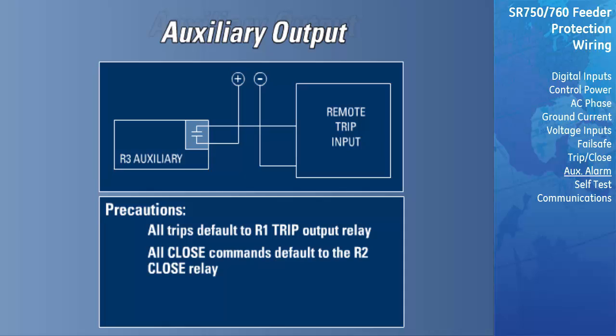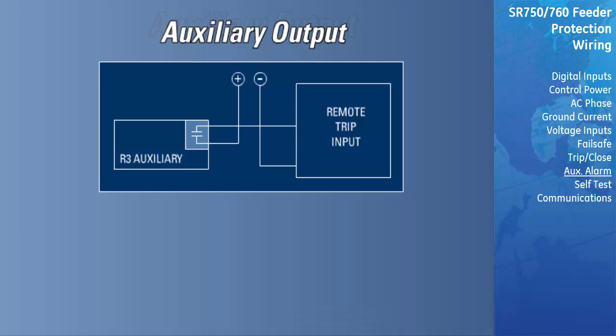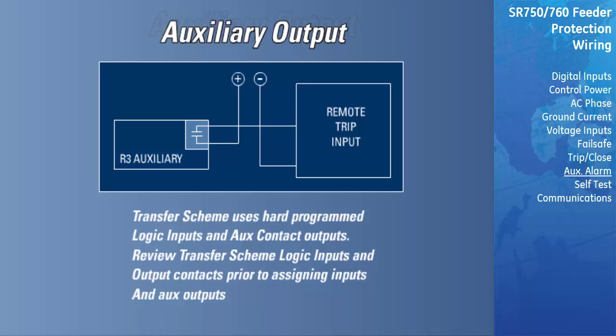If the transfer scheme is going to be implemented in the relay, there are a number of logic inputs and relay outputs required for specific functions in the scheme. Please review the transfer scheme for the required inputs and outputs prior to assigning the output contacts of the relay.